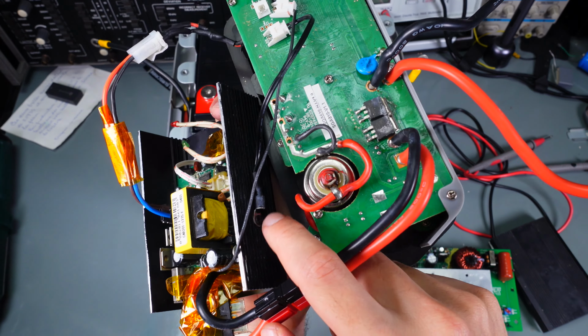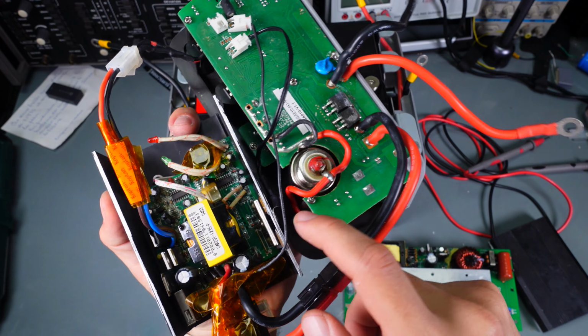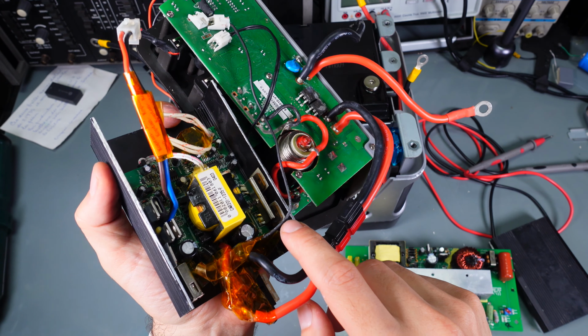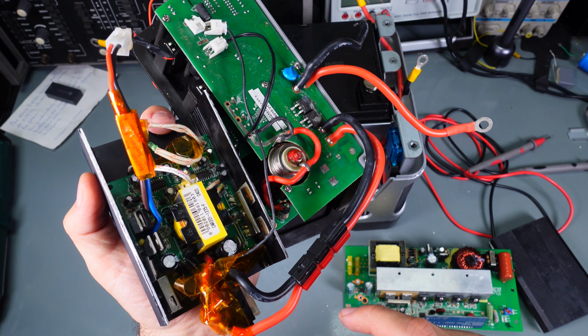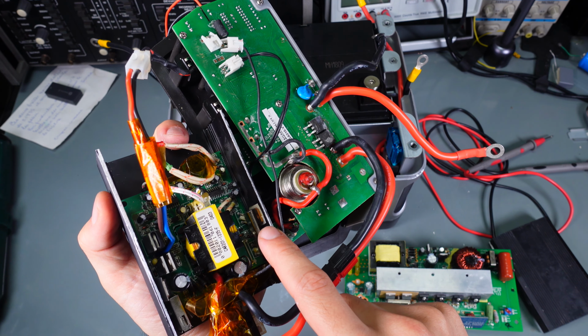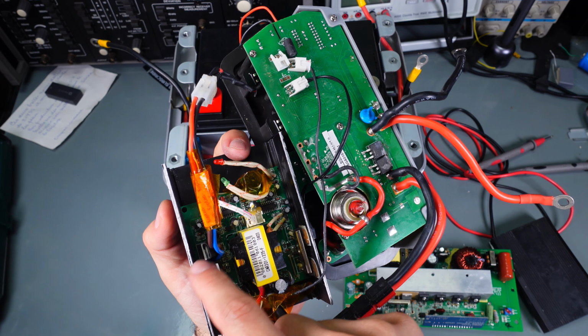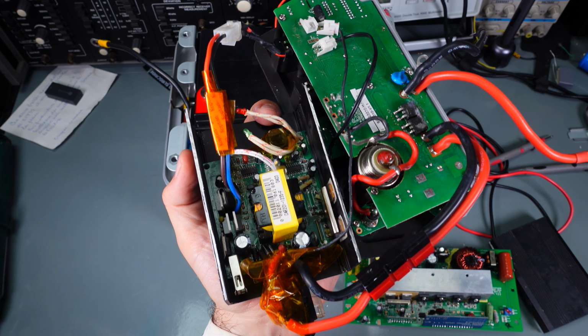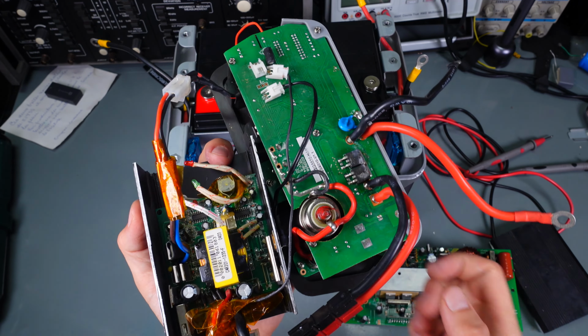I've decided to put the thermal probe onto the low voltage side because there will be a much higher current, so there will be more losses. On the high voltage side there should be no problem.